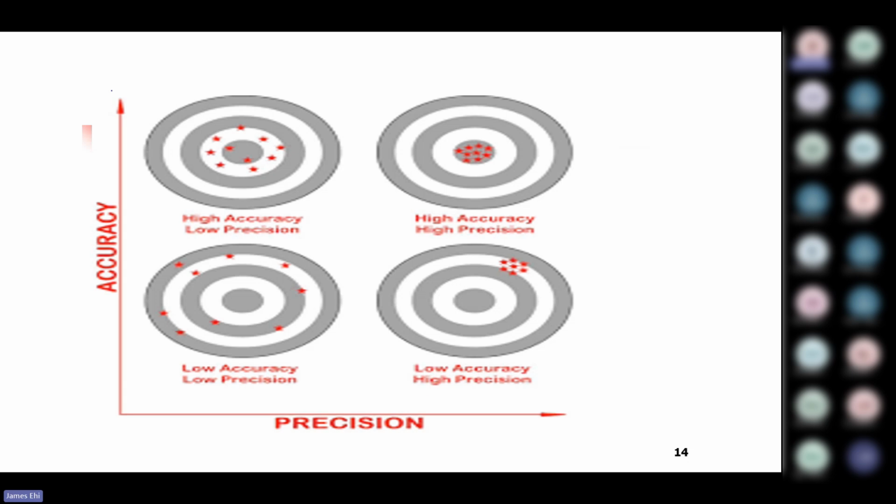The same thing happens with your analytical system. The fact that you have set it up to run accurately doesn't mean that it remains there. With time, per reagent shelf life on board, especially those that have reagents staying beyond the expected shelf life, those that go longer between calibrations than expected as stated by the manufacturer's instruction, or even sample volumes. If your sample volume is so high, you might need to recalibrate more often. So that will bring you into four possibilities.